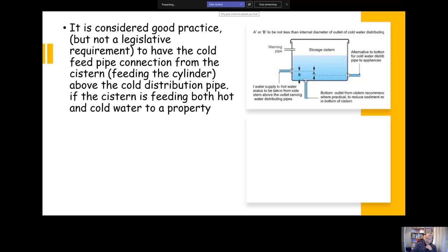If the mains get switched off for whatever reason and people have been using water throughout the day, the water level will start to fall in the system. Say for example someone was having a shower with a manual shower valve, the water level's falling here. If it fell below the cold distribution, the cold would switch off and then you'd just have hot water coming through and somebody could get scalded. So if you take your cold feed, which fills up your hot water side, off above the cold distribution, that means that the hot will switch off first and the worst that will happen is someone will get cold rather than get burnt. That's not a regulatory requirement but it's something that's considered good practice.